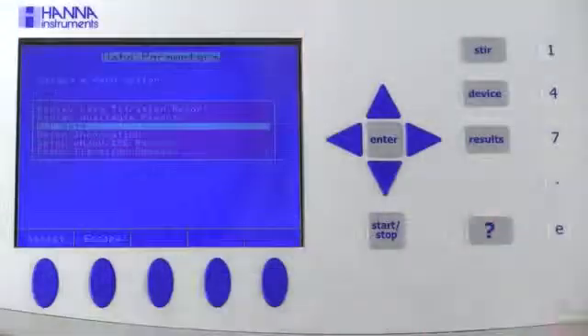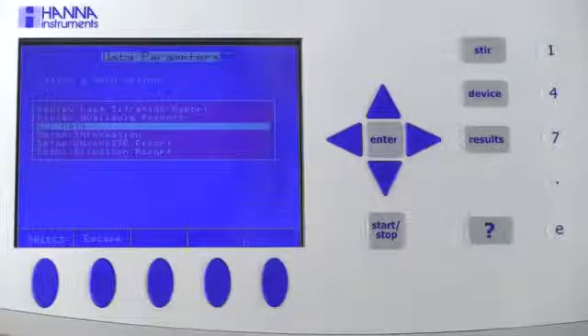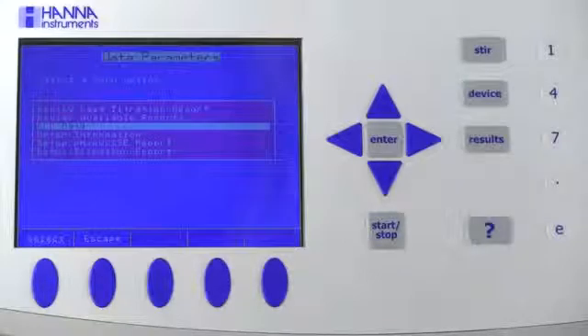Press the results button to access the data parameters menu from any mode. Here, you can elect to set up pH millivolt ISE report, set up titration report, or set up GLP data.